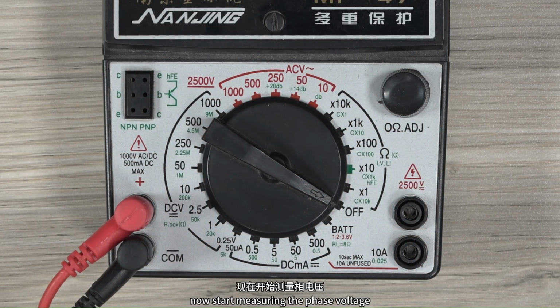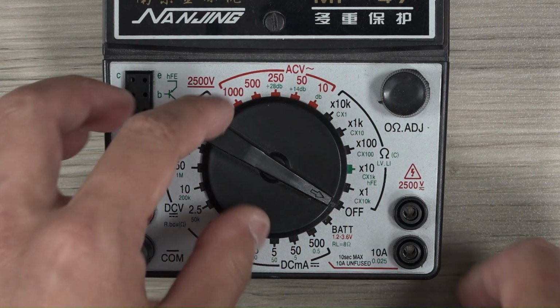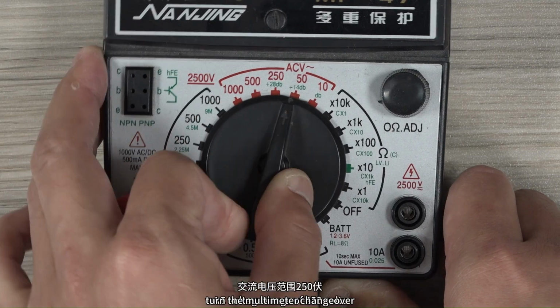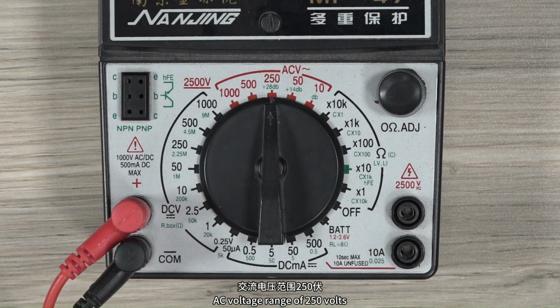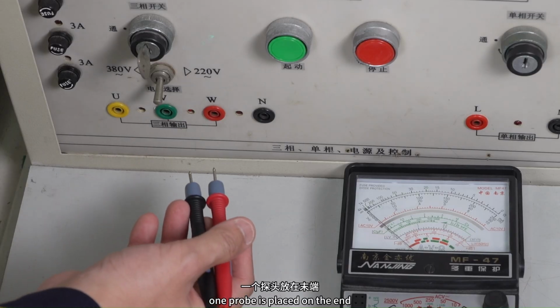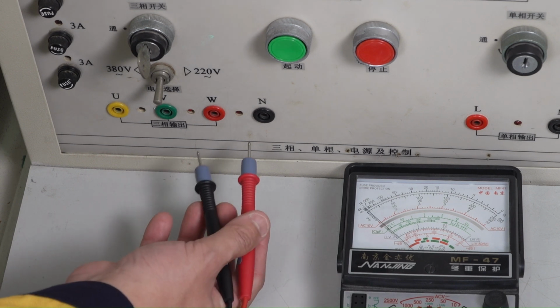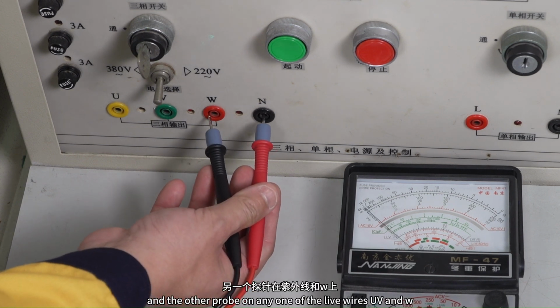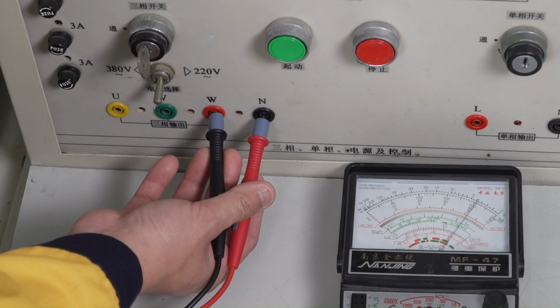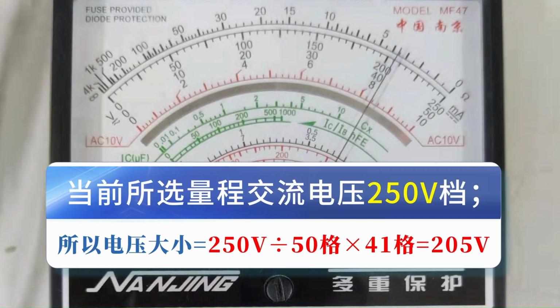Now start measuring the phase voltage. Turn the multimeter changeover switch to the AC voltage range of 250 volts. One probe is placed on the N end, and the other probe on any one of the live wires U, V, and W. The measured voltage is equal to 250 volts, divided by 50 grids, and then multiplied by 41 grids, which equals 205 volts. Measurement completed.